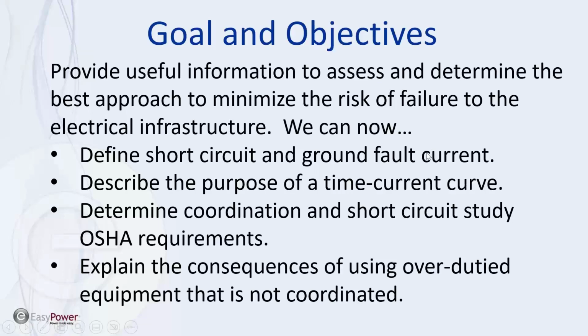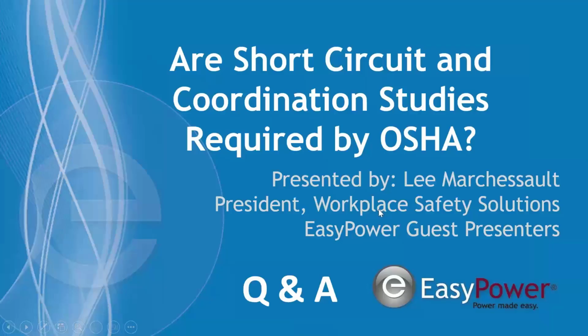And that's pretty important. So hopefully we defined the short circuit and ground fault, what they are. We talked about the purpose of time current curves for both coordination and short circuit, for tripping and so forth. And then we talked about the coordination and short circuit study with OSHA, and got into some of the consequences of having overduty equipment that is not coordinated. Okay, and that's the presentation for today.